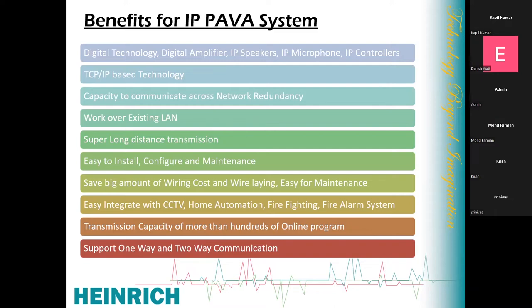Super long distance transmission: wherever your network is reachable, our PA system can be installed there. In digital or analog systems there is a limitation — you cannot run speaker cable beyond 800 to 1000 meters, and you cannot install a second controller beyond 300 to 400 meters from the first. But with an IP system, if there is a network on your premises, you can install controllers or amplifiers anywhere. There is no distance limitation.